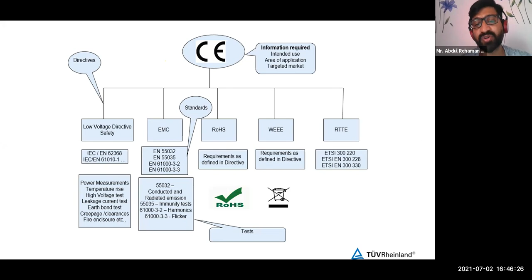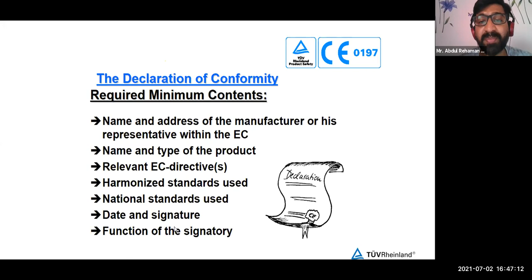The declaration of conformity, what does it require? These are the minimum contents which have to be there when you are declaring it: name and address of the manufacturer, type of product, which directive has been selected, whether the standards are harmonized, whether national standards are used or not, signature, date, and the function of the signatory. This is the basics of the CE directive.